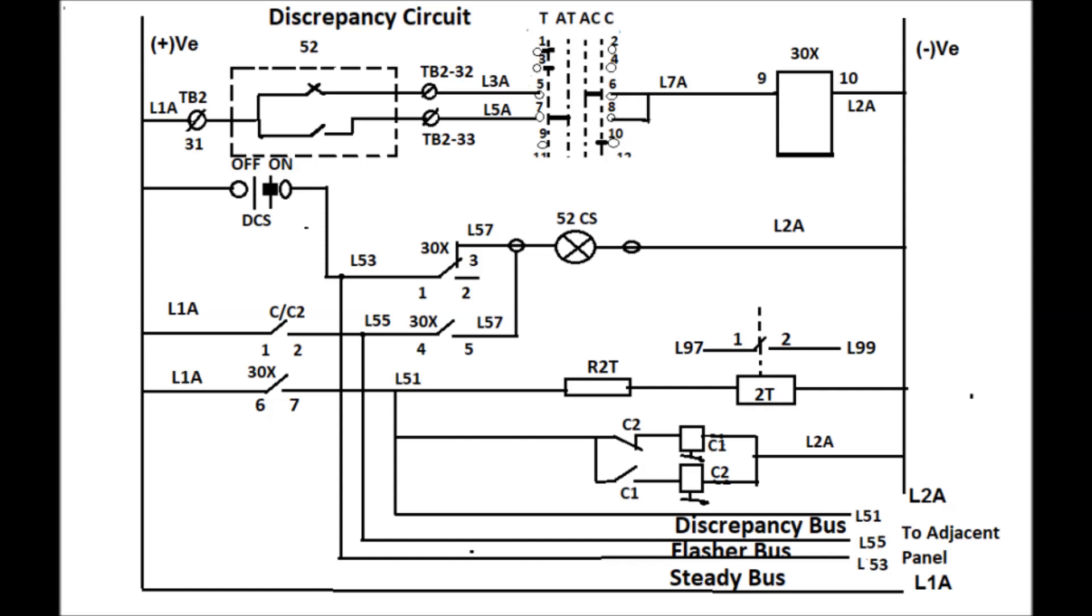One flasher relay located in the bus coupler or bus transfer panel. Actually, there exists only one flasher relay in the entire 132 kV or 220 kV systems. Discrepancy relay in each panel, if any discrepancy happens with the position of the control switch and the CB state, it will lead to operate the 30x of the panel.